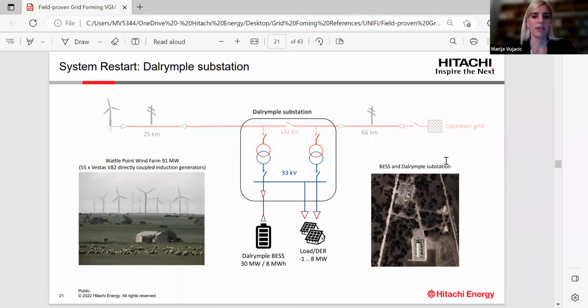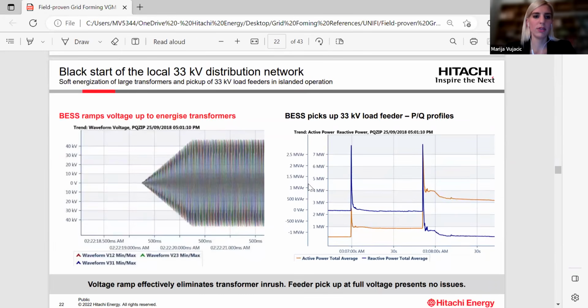Another important feature or capability of the battery energy storage system, which was demonstrated in ESCRI, was black start. This was done by soft energization of the battery energy storage system transformers and the 33 kV network. So we can see here that the battery energy storage system ramped up voltage over a 1 second time. This was done to avoid inrush currents of the 33 to 132 kV transformer.